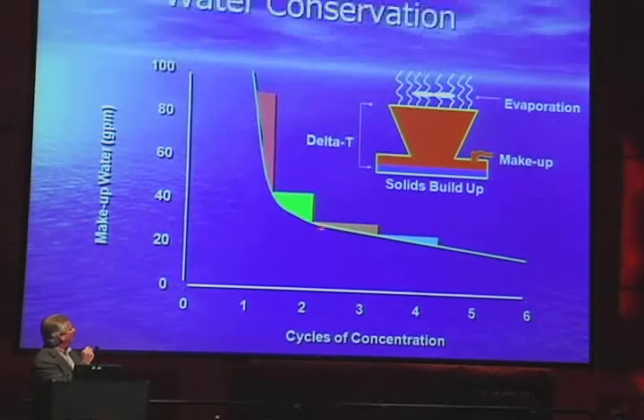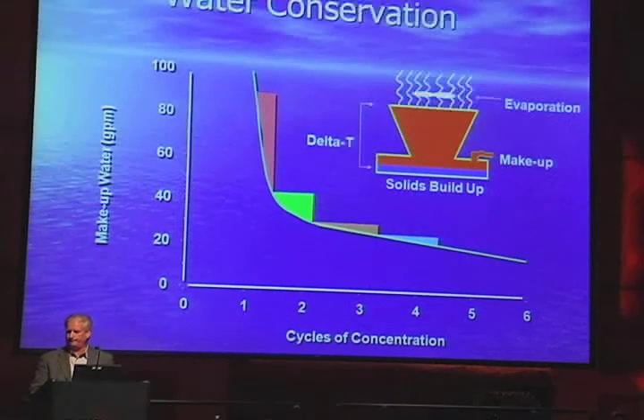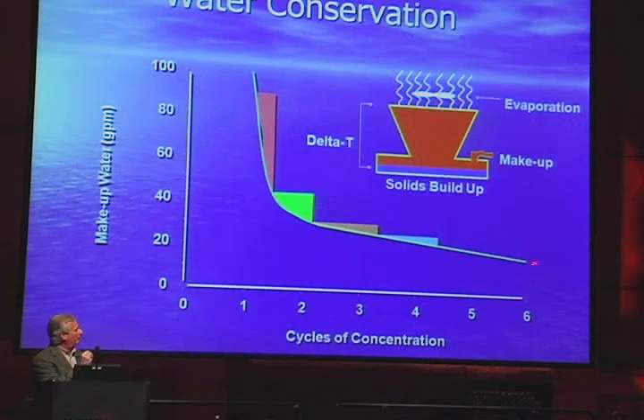From there, for 3 cycles, you drop a fairly good incremental amount. 4 cycles, 5, 6, 7, 8, 9. There is a diminishing return. You can see the graph coming down, and eventually it's going to go way out here. It'll never reach 0, obviously 0 discharge, where you just don't discharge anything. So you can see the incremental savings here is not as great, but still worth capturing. But if you're running up in here, then the savings are very drastic.